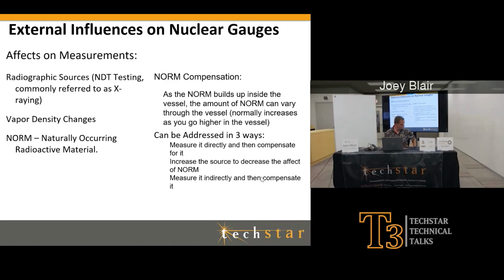This is great. Walter is asking, what will be the lowest level of radiation a detector would see when empty and still be a usable system? The lowest level that it can see when empty. So you're saying at the 0%. There's really not a straight answer for that. Preferably, the more radiation I see, the better. So I like to see 1,000, 1,500. I like to see good numbers. I have made measurements as low as 200 or 300. Well, maybe not that low, maybe about 600 counts, 500 counts, 400 counts. I have seen them make measurements and be reliable at those points.